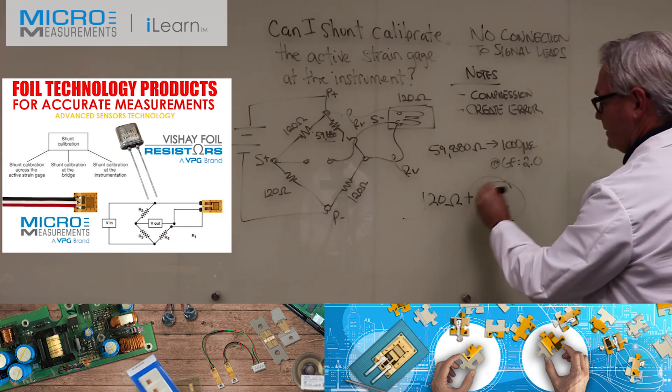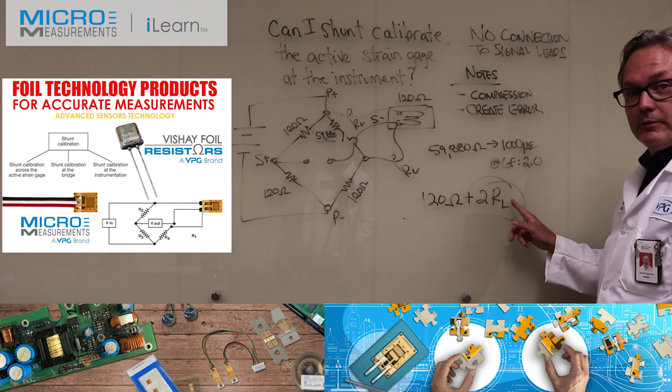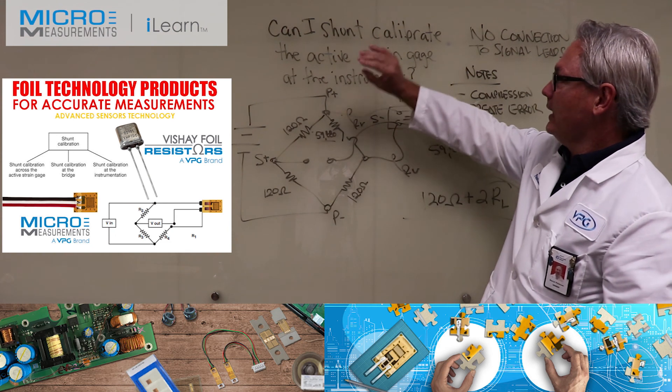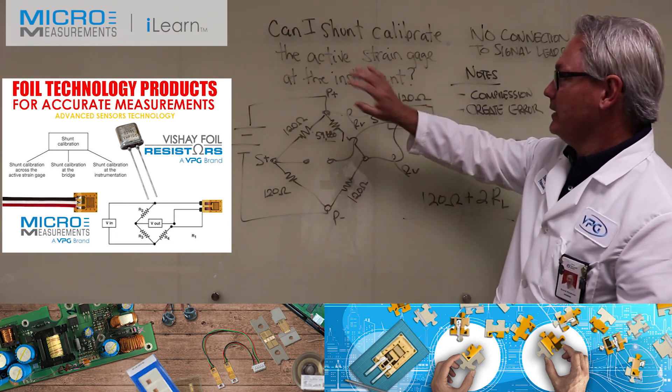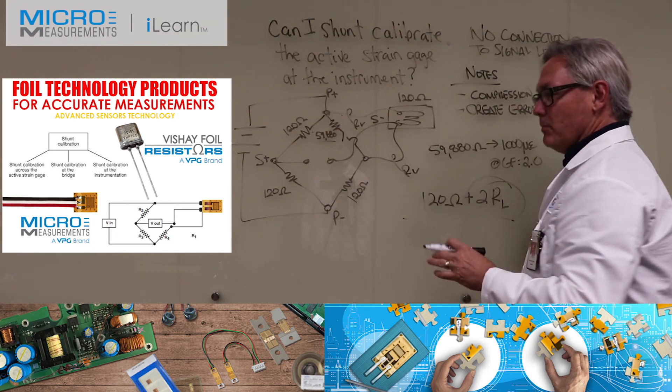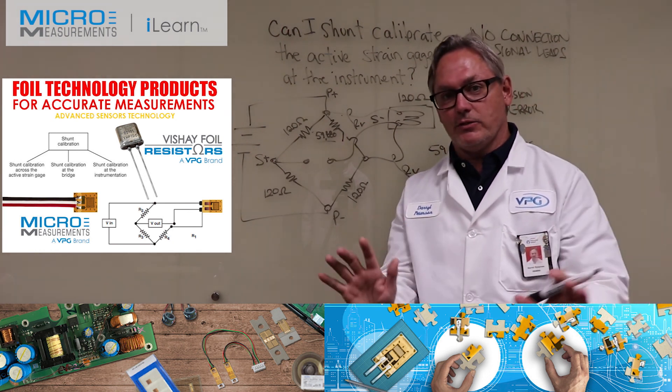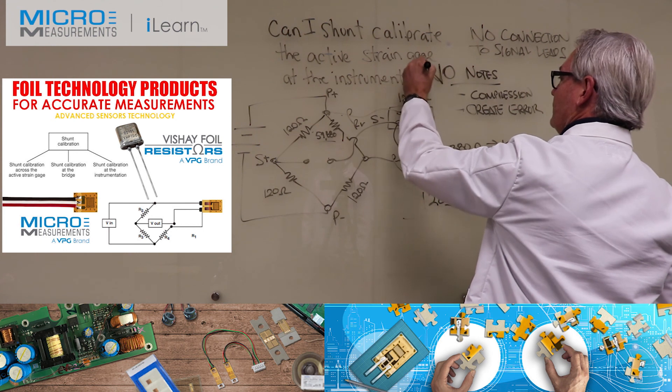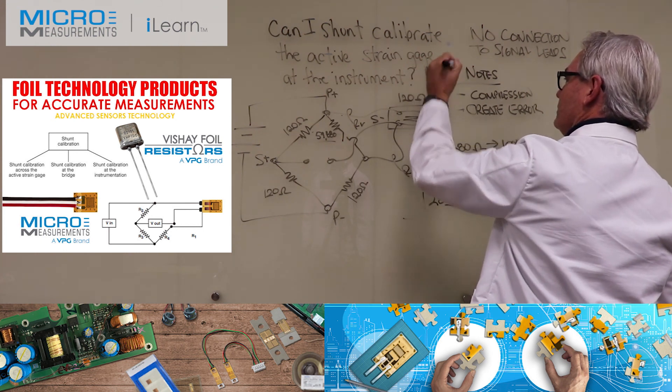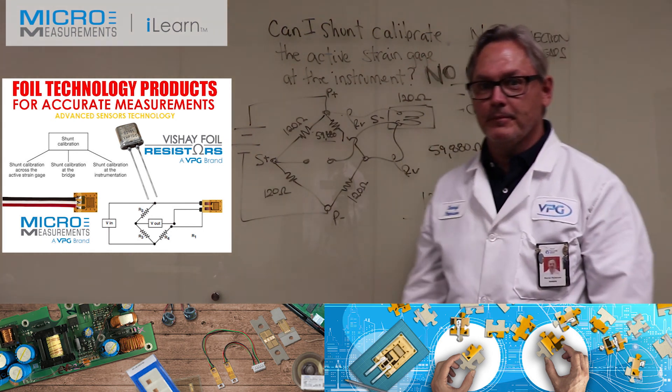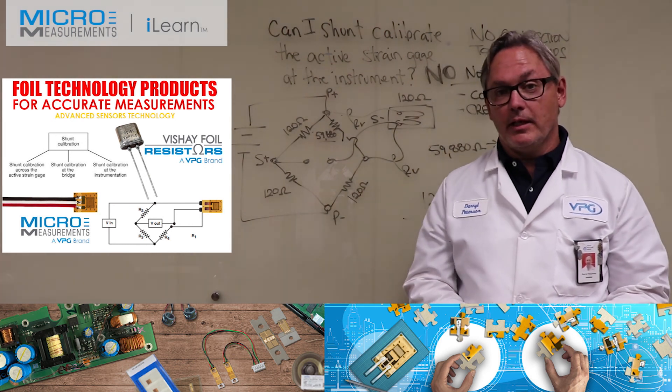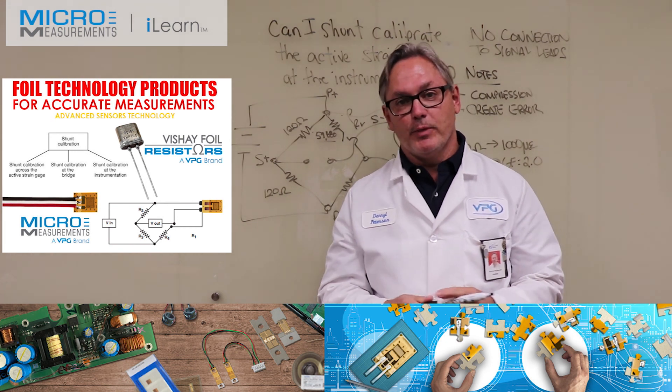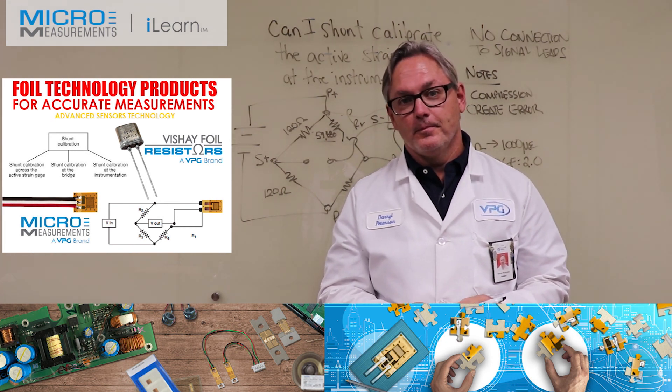This will vary greatly depending on your application. So to go back to the original question: can I shunt calibrate the active strain gauge at the instrument? For most applications and customers I would say no - there are better places to calibrate, don't do it there. If you'd like to find out more about shunt calibration, please visit our website at www.micro-measurements.com. Thank you.